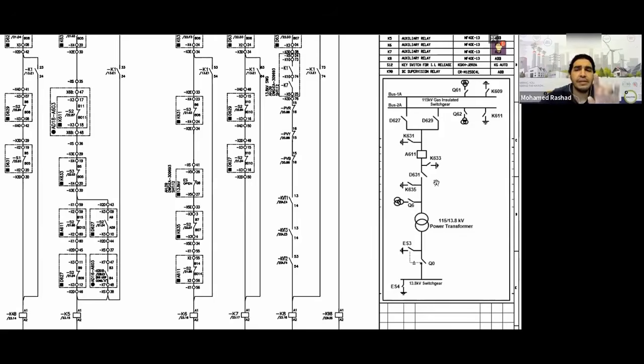Of course, if you weren't going to check anything more than this, the ground and the breaker should be open. And if you know how to work on it, and your client allows you to perform any action you want, I have done this before at a station using, for example, the SEL411L relay or the MiCOM P546. I have done it on the RED670 and the REL670, and on the 7SD using the 87L communication through fiber optic, which is the remote signal, or what they call the inter-MiCOM, for example, in the MiCOM relay, or the remote signal in Siemens, or in the SEL relay, which use communication bits. The important thing is that I can load some digital signals onto the fiber as I want.